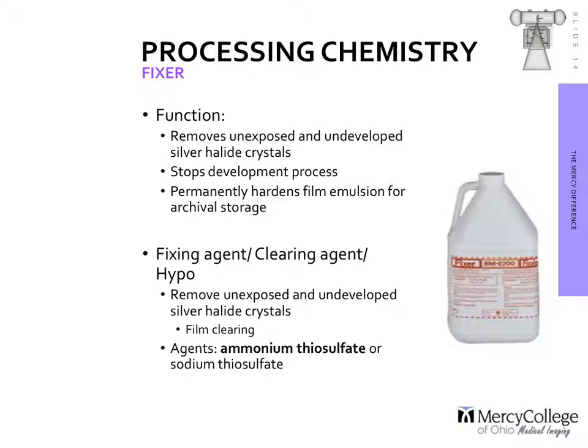Just like the developer had a series of agents associated with it, the fixer is the same. It doesn't use the same agents, but it has a lot of agents that are associated with it. So do recall the function of the fixer as indicated here, so that's important. But also understand that, like the developer, it can come in multiple different forms. It can come in a ready or pre-mixed form. Certainly it's going to be easier, ready to go, but it's going to be more expensive as such. It could also come in a concentrate form. This is going to be cheaper, less convenient in that it's going to have a two-part kit that must be mixed with water. The water is going to have to be mixed appropriately in the correct amount with the fixer.